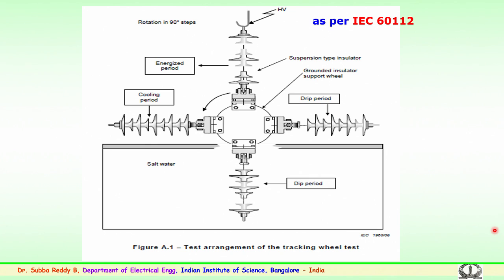This is a very important experiment, and fabrication and simulation of this facility requires significant effort — particularly in implementing a suitable sensor mechanism, relays, and timers, since the experiment runs for more than 1000 hours. Several thousands of cycles must be done continuously, with breaks as mentioned in the standard: after 8 days of operation there is a 1-hour break for changing the contaminant in the tank. This experimentation is very important for aging analysis of polymer insulators.